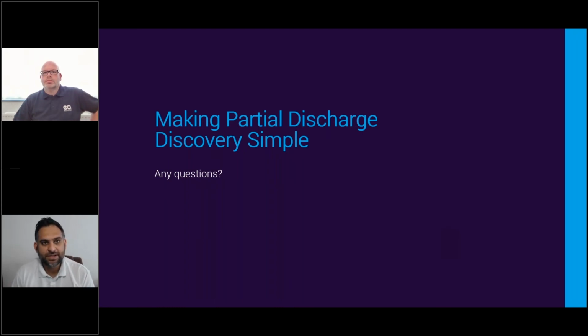In a typical HV substation, you normally have a transition joint just outside the substation building, and then the last 5 to 10 meters are within the substation itself. So for those 5 to 10 meters, you can use the instrument, and just by placing it onto the cable itself, you can pick up PD activity that way.